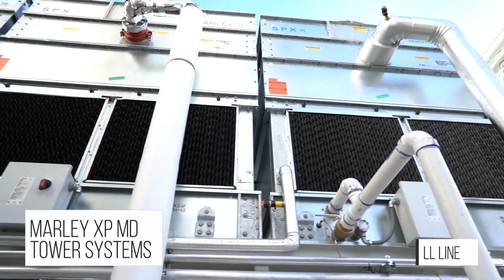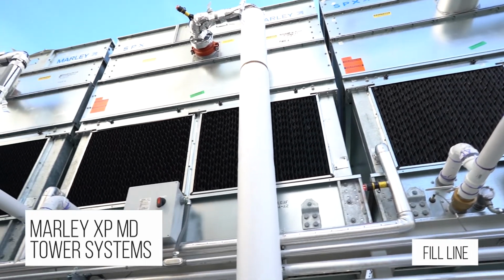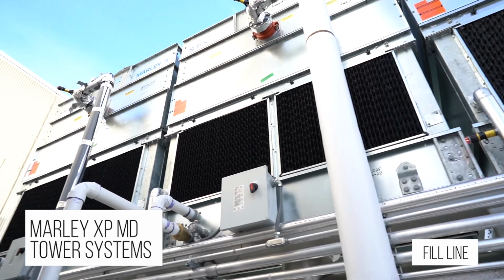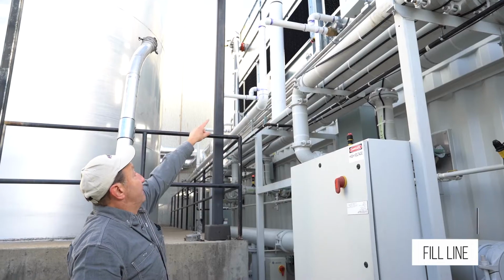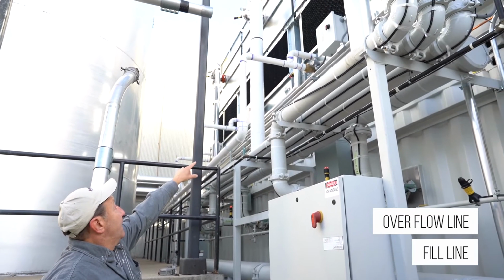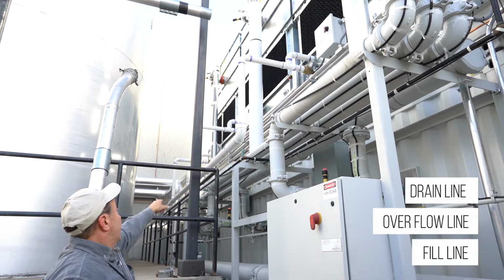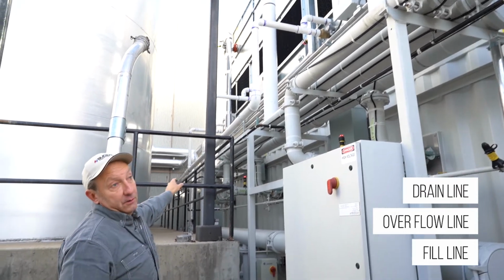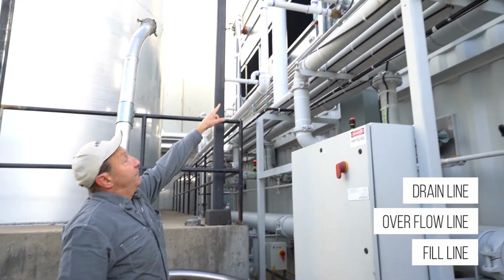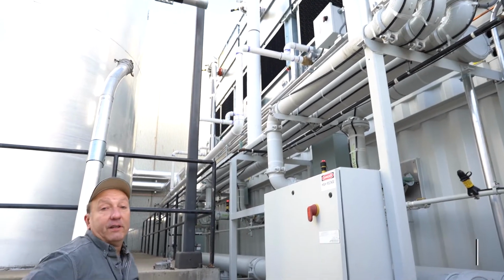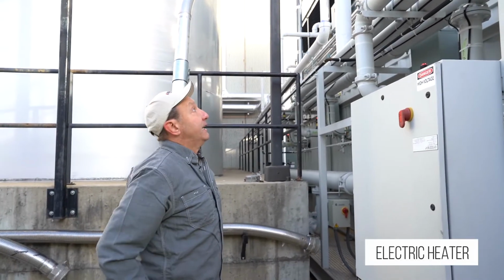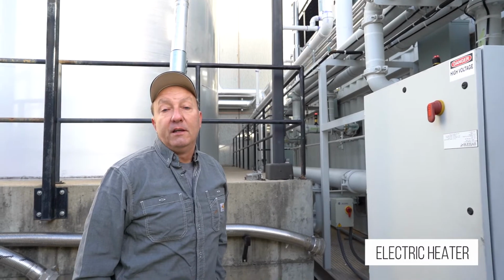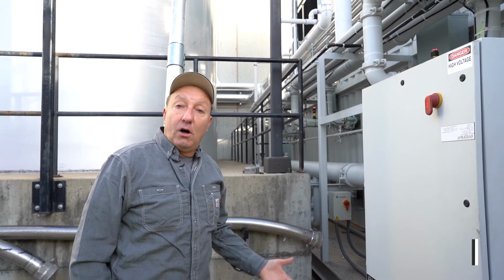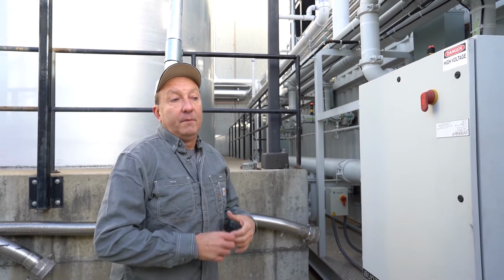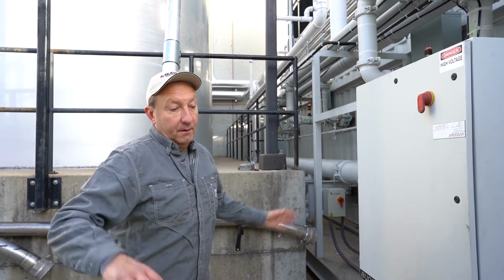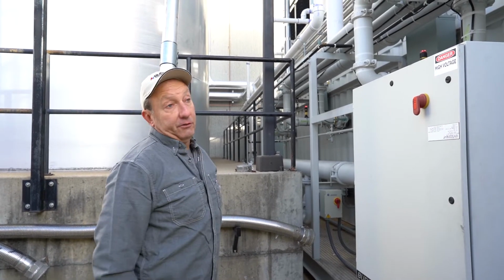We have a fill line that's covered by the insulation and the heat trace. That is complete so far. We have an overflow line and a drain line. The drain header goes back into the building into a sump pump. Each basin has an electric heater. It's 6 kW and it keeps the water from freezing when the system is not in use or off. It keeps the water warm and doesn't allow it to ice up and freeze the basin and restrict flow.